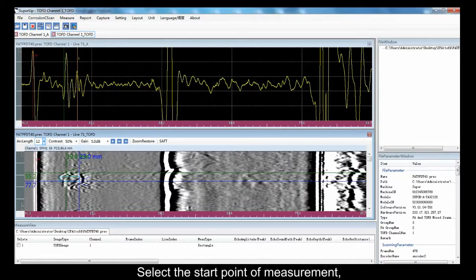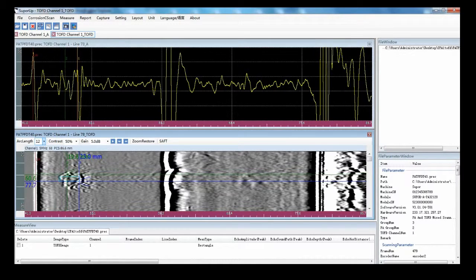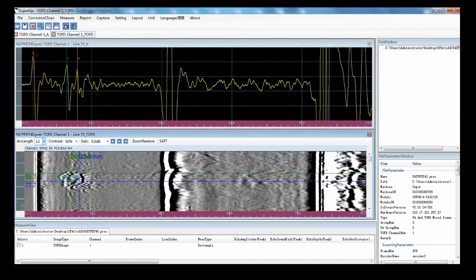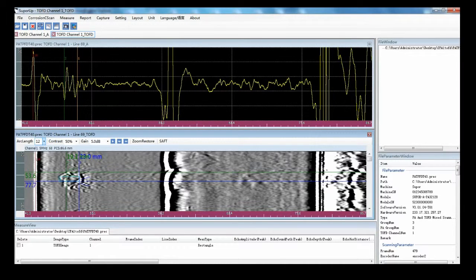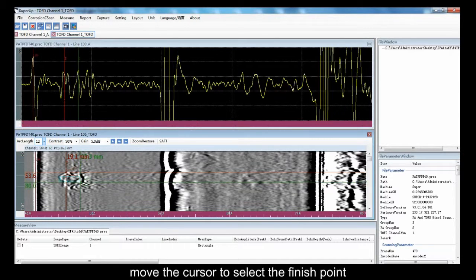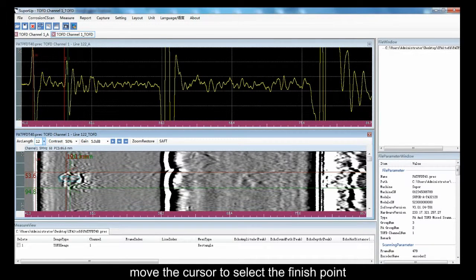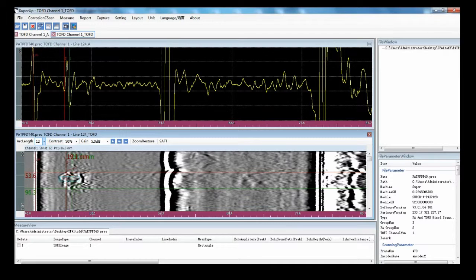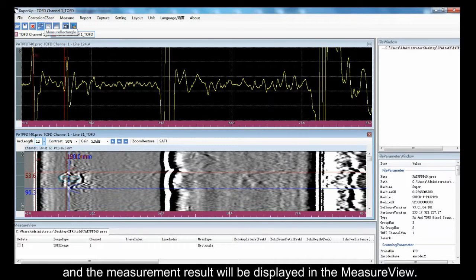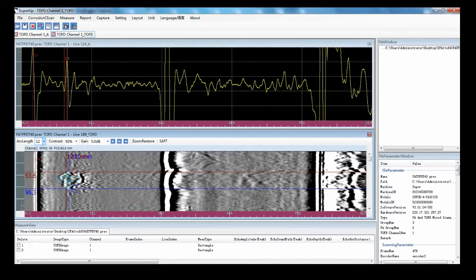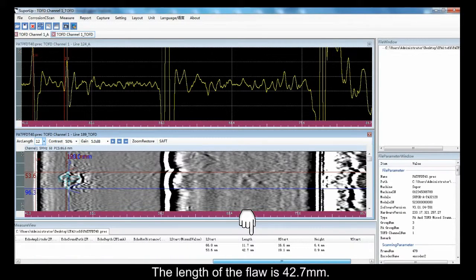Select the start point of measurement. Move the cursor to select the finish point. And click Measure Rectangle, and the measurement result will be displayed in the Measure view. The length of the flaw is 42.7 mm.